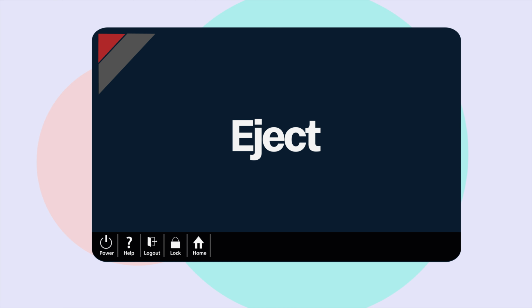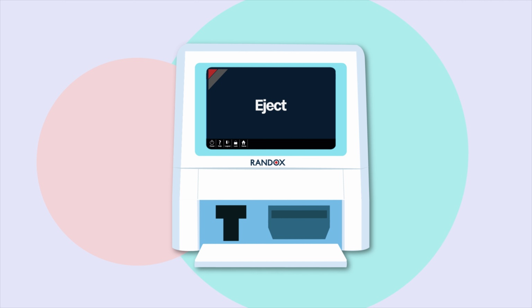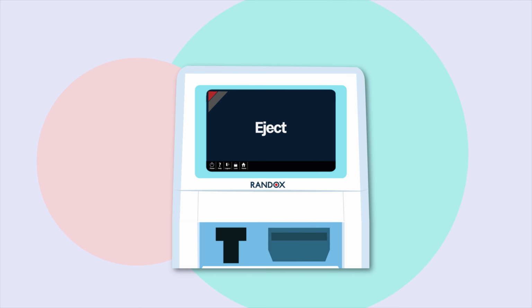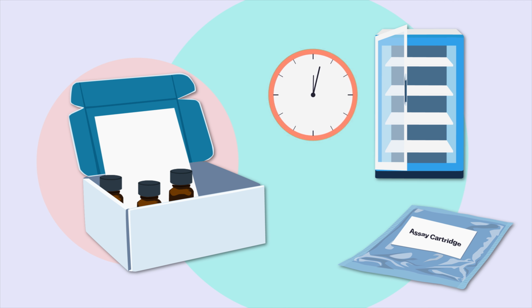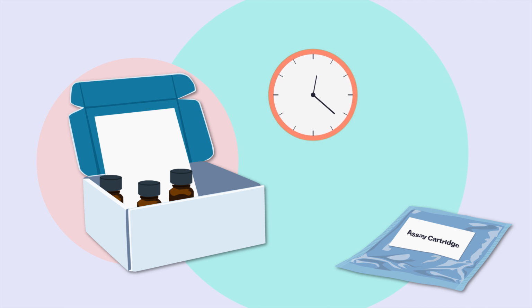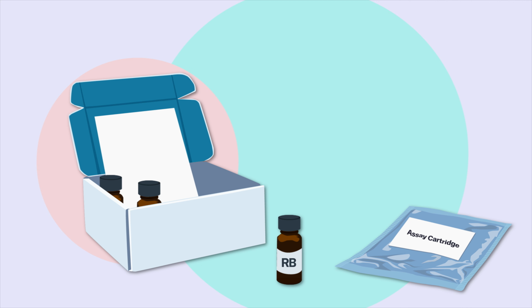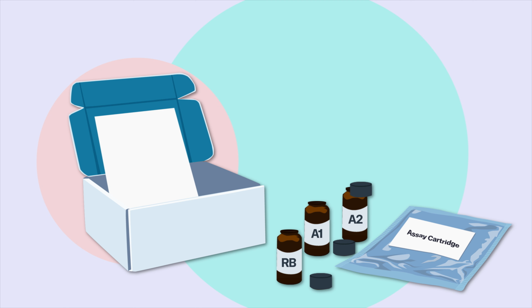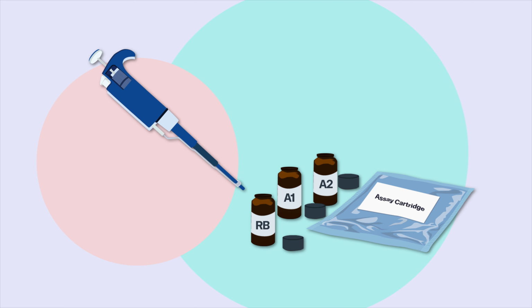Then click Next. Tap the screen when prompted to eject the drawers. The door will then open automatically, followed by the cartridge and tip drawers. Leave this open whilst preparing the adjusters. Take one assay cartridge from the kit out of the fridge, but leave it sealed at room temperature for 30 minutes. In the meantime, remove 1 vial of reconstitution buffer and 1 vial of Adjuster 1 and a vial of Adjuster 2 from the assay kit.